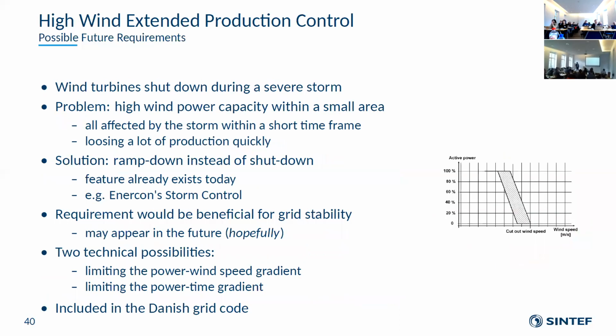The other one is high wind extended production control. Normally wind turbines shut down during a storm, which is nice, but in the long run, if you want to run the system based on wind power, we can't just keep doing this shutdown. Because the geographical density of wind power gets so large, when a storm hits you lose a lot of production within a short time, since all the turbines in the region will see the same storm front within a short amount of time. So the solution is that you cannot just switch down the power, but you ramp it down instead. This already exists today.